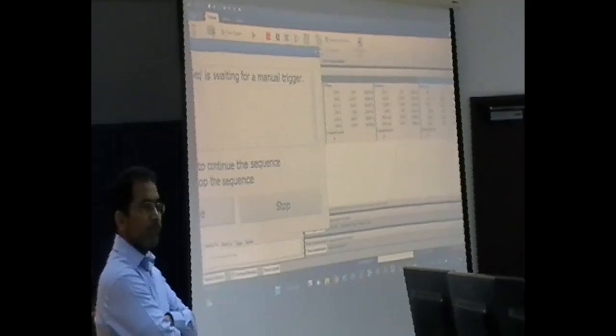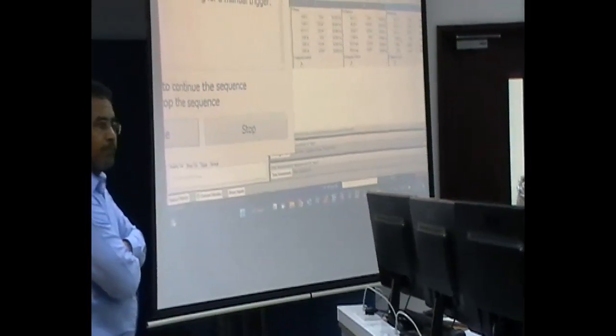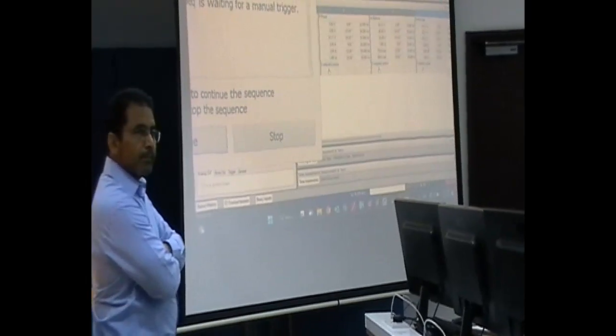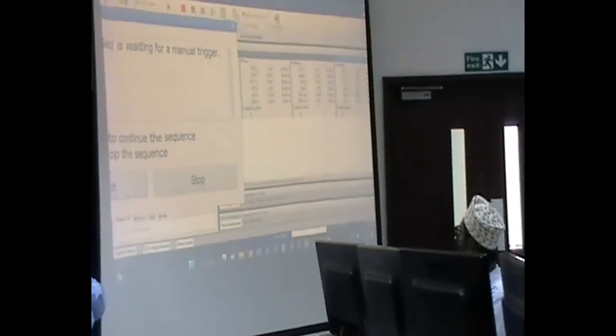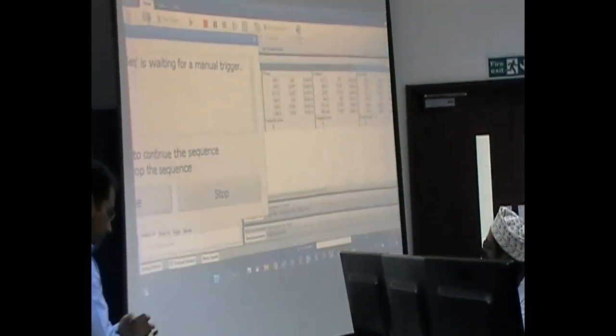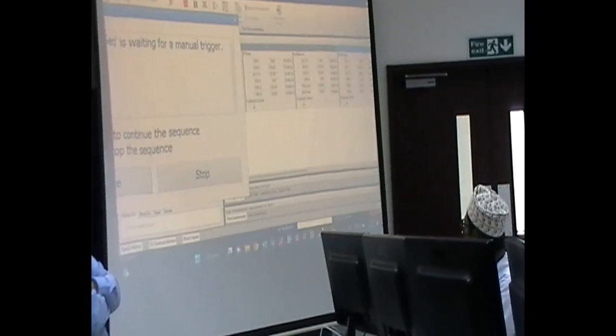In the next test, I will inject only positive sequence because it's balanced, so I'm not expecting any negative sequence or zero sequence. This is 63.5 volts at 0 degrees, then the same magnitude at minus 120 and the same magnitude at 120, and all 1 ampere with balanced angles. So during test number 5, am I expecting any negative or zero sequence? There should be none. I'm communicating with the relay, so whatever appears here is from the relay. Now you can see it's 400 ampere, which is basically 1 ampere in the injection, in all three phases.